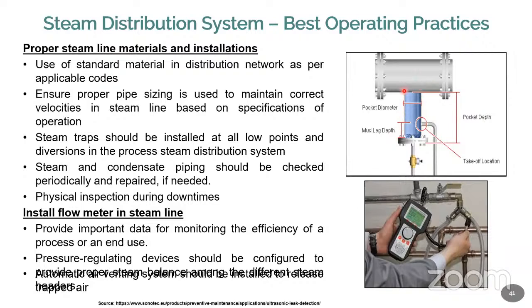And at a diversion of the process. We have a diversion here, a T connection, a diversion of the process in the same system. You can see the steam and condensate piping should be checked periodically and repaired, because if there is any problem in the steam, or in the recovery rate of the steam condensate, that would be a good indication for saving energy. And physical verification of the data should also be there.